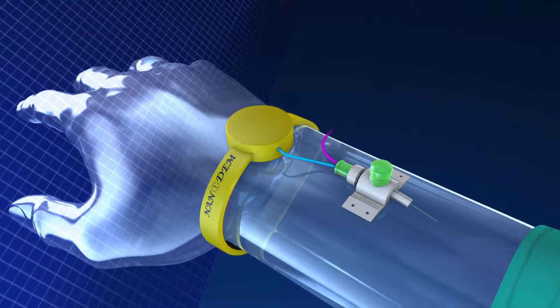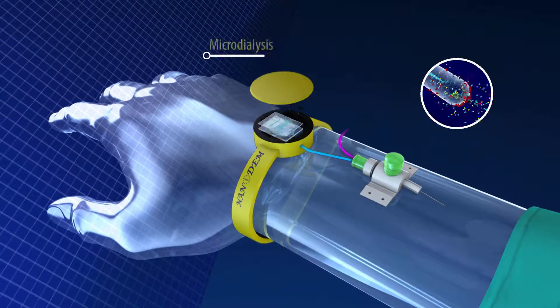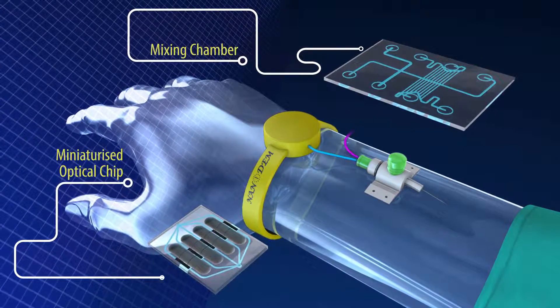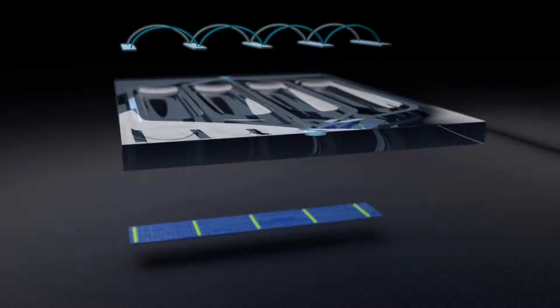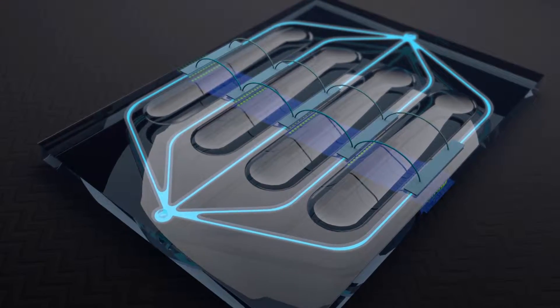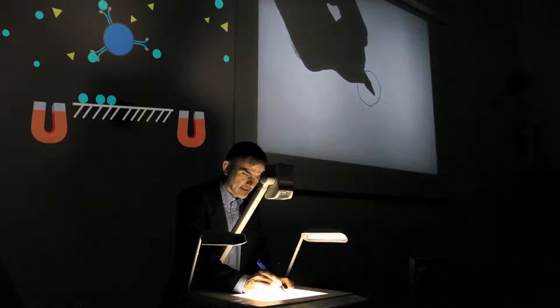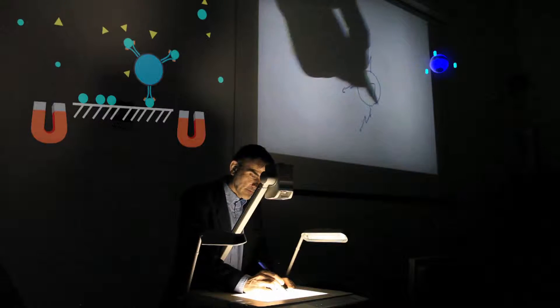The patient is connected to the device to allow continual measurements. Samples drawn from the blood are mixed with the chemicals necessary to perform multiple tests. Miniaturization down to micron and nanoscale makes it possible to perform multiple measurements within each hour. The samples are pumped through a dedicated chip where the different drugs and their concentrations are determined. At the heart of the device, there will be a multi-parametric optical chip to convert the drug concentration change into detectable light signals.